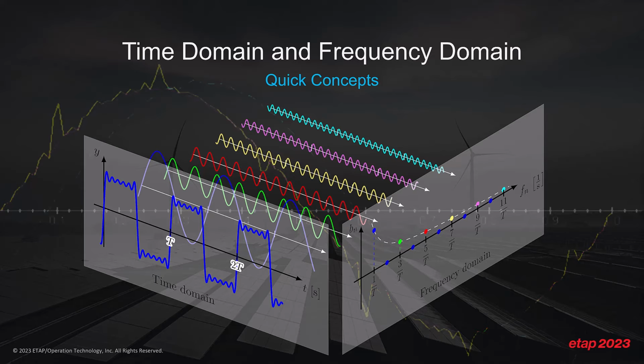Transformers, for example, are especially susceptible to damage caused by harmonics due to stray eddy currents that can circulate in the iron core and produce excess heat. Harmonic analysis is done using Fourier transform and other signal processing techniques that are used to analyze the impact of harmonics on the power system.